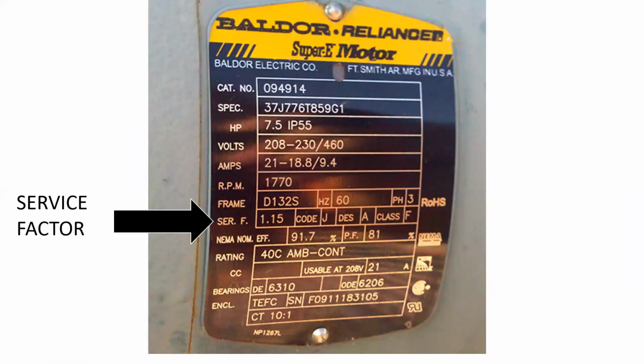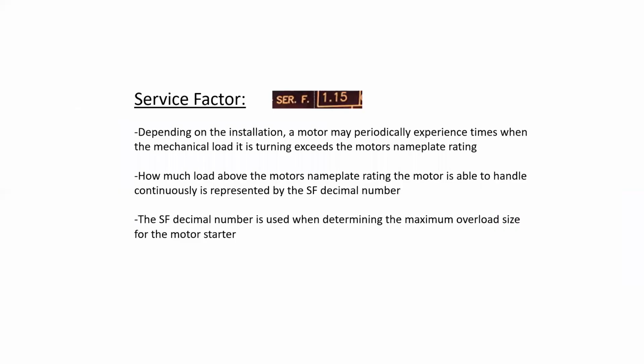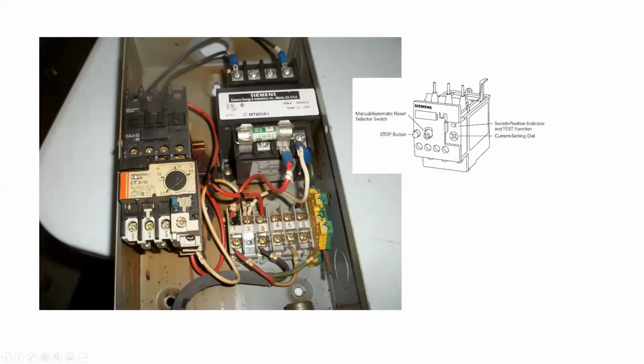Service factor. The service factor for this motor is 1.15. Depending on the installation, a motor may periodically experience times when the mechanical load it is turning exceeds the motor's nameplate rating. How much load above the motor's nameplate rating the motor is able to handle continuously is represented by the service factor decimal number. This service factor decimal number is used when determining the maximum overload size for the motor starter, and we find information for that in Section 28 of the Canadian Electrical Code. The overload, of course, on a magnetic starter would be the assembly that mounts to the load side of the contactor, which is right here. That's the contactor, and the overload is down below. We would set the dial to the maximum calculated overload permitted, and that would be based largely on the service factor.